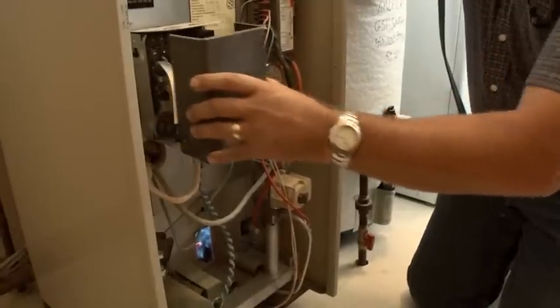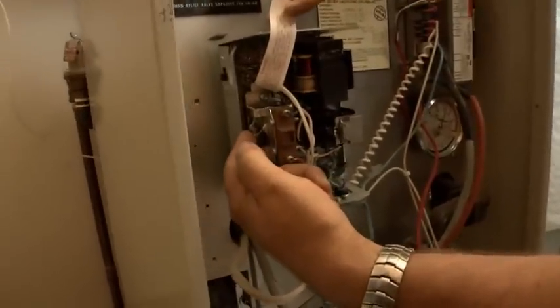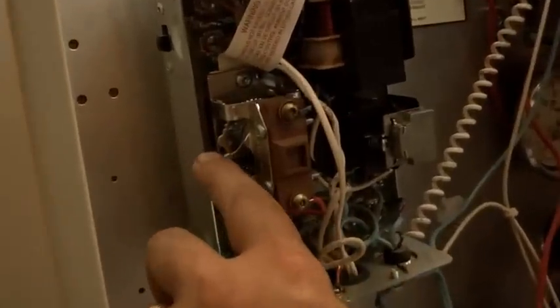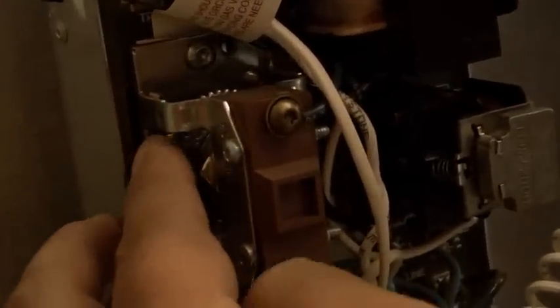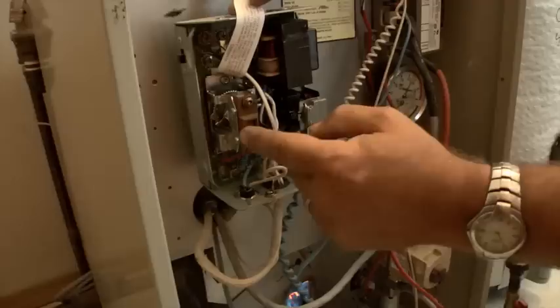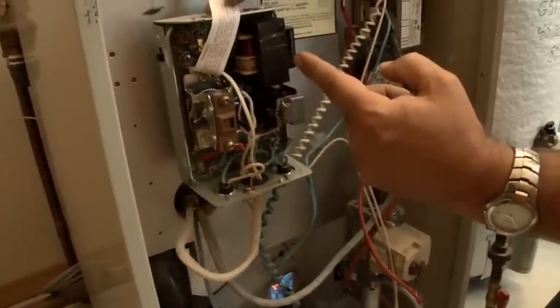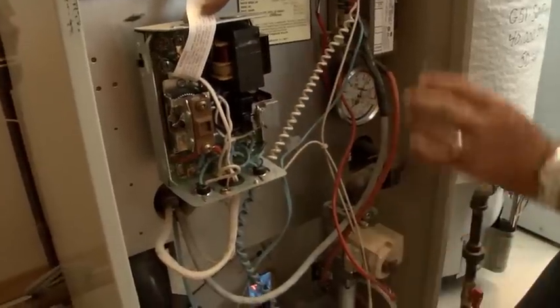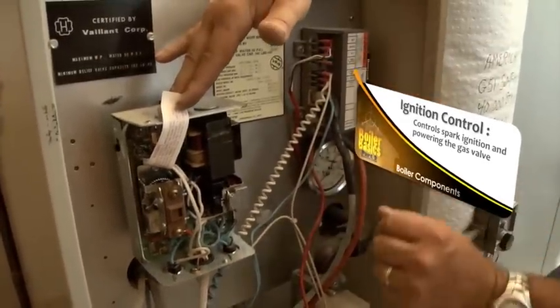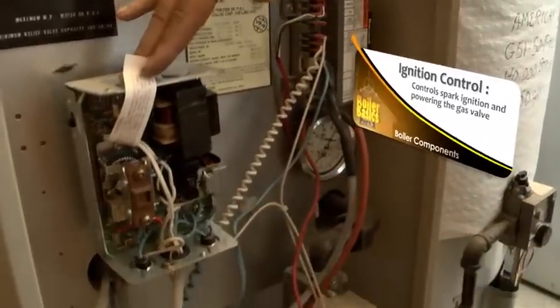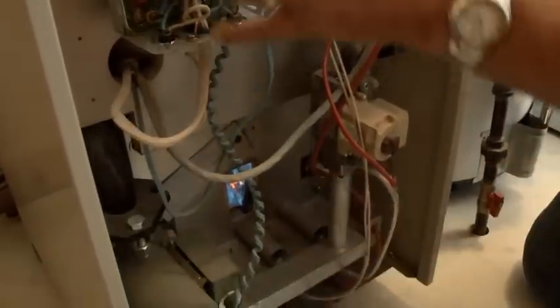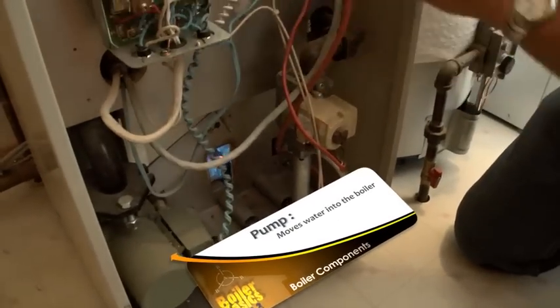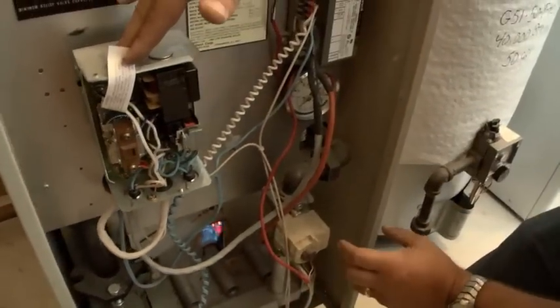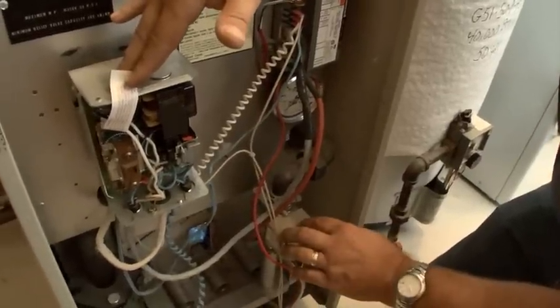If we take a look inside the aquastat, there is a dial. Right here's the dial, and this dial turns, and it's set for right at about 180 degrees, and that's where we want to have it set for this heating system. So here's the aquastat. It also has the transformer that provides the 24 volts to run the gas valve and the ignition control, and then also a relay that turns the pump on when we get a call for heat. So this is part of the brains of this thing, and then this is the part that controls the ignition and the power to the gas valve.